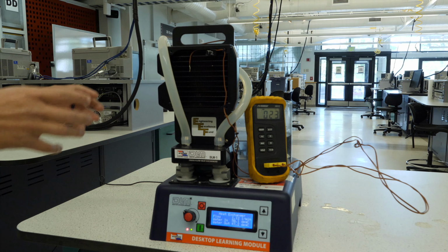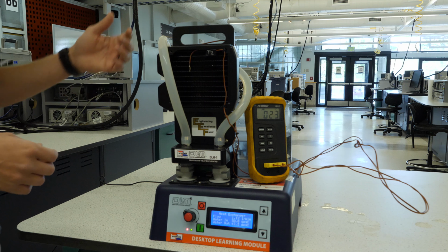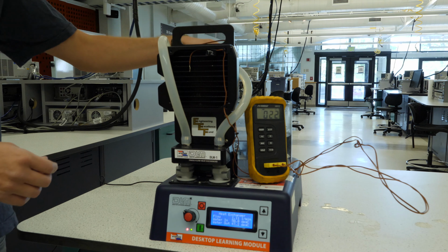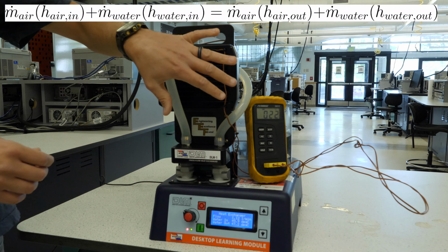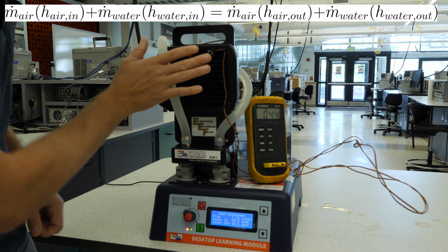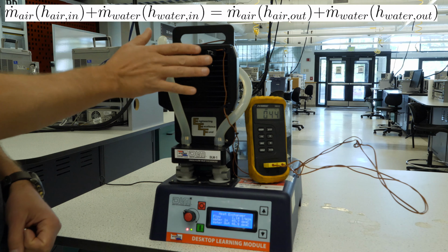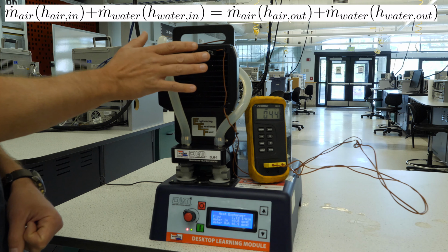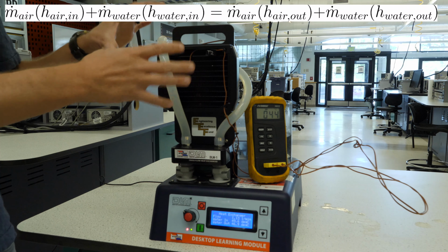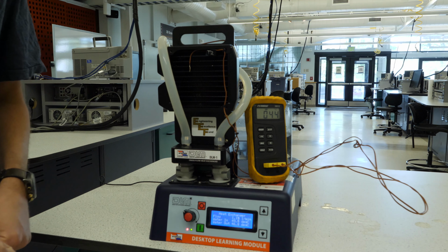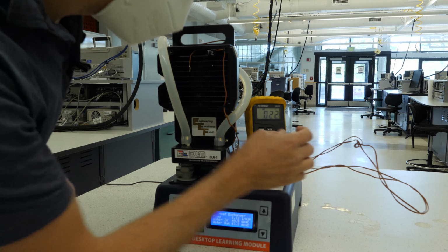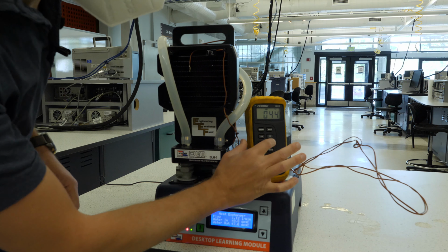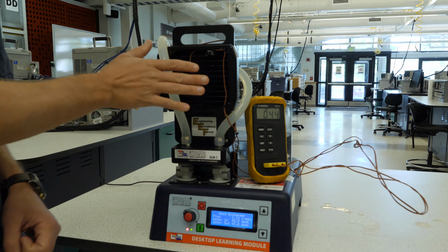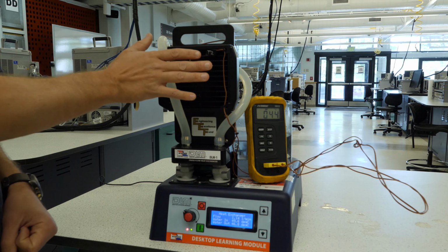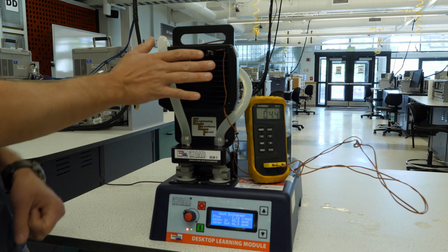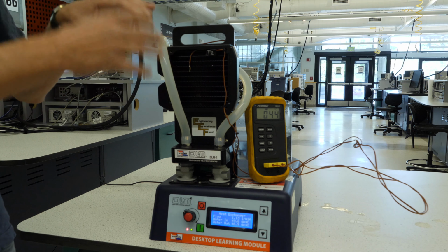And so the flow rate, right now, is reading 1.11 liters per minute. And we could do an energy balance of this system. We could figure out what the total heat exchanging is. So the heat is being transferred from the water to the air, and that's why it's heating up the air and cooling down the water. If I look at the temperature of the air flowing out, the air is 44 degrees Celsius as it moves out. So it's pretty warm air as it comes out of that heat exchanger, and so there's a lot of heat being added to the air.